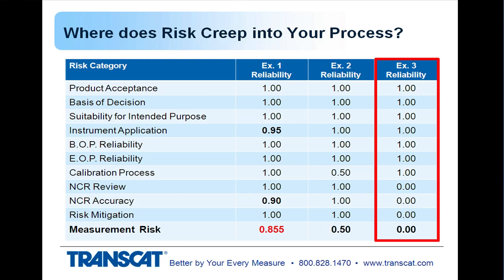Example 3, reliability would say that you don't have an NCR review process at all. I've seen situations like this, although it's not very common. But that's the point of the whole traceability chain of measurement: not only to make sure that you have equipment that's suitable for the intended purpose, but make sure that you're using the end result of the calibration of those instruments to determine whether you have an impact to the product. And if you're not reviewing the results of those out-of-tolerance conditions, and in some cases in-tolerance conditions that are close to the limit, then you're not doing yourself any favor. You're throwing away good money for the calibration process and the use of the instrumentation to control your process.